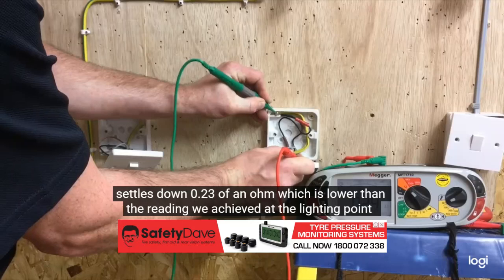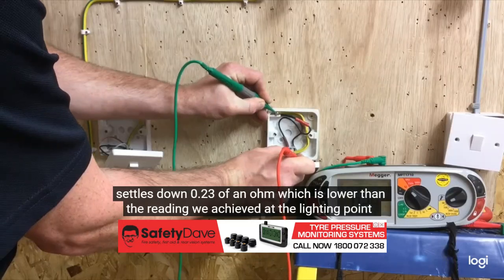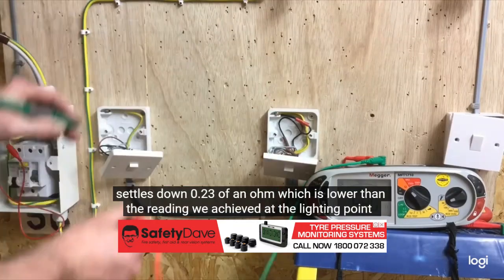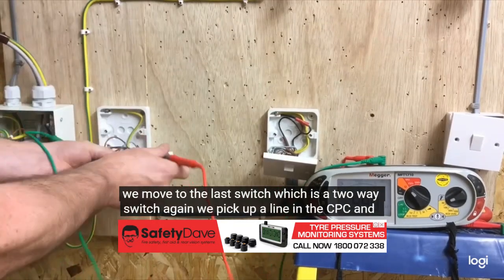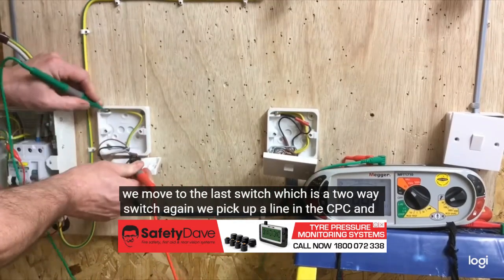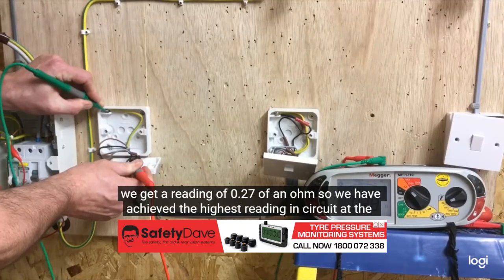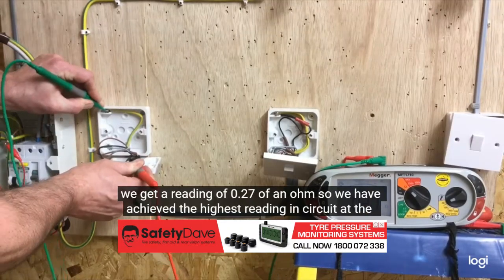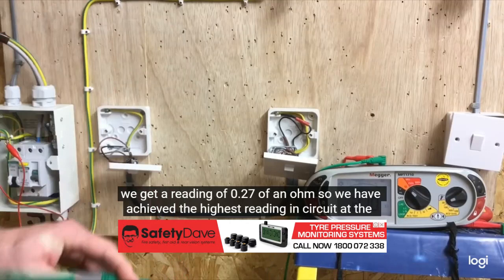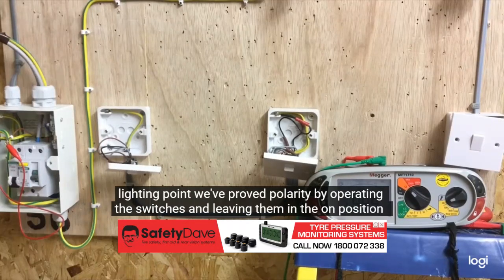We've got a reading of 0.27 of an ohm. So we have achieved the highest reading in circuit at the lighting point. We've proved polarity by operating the switches and leaving them in the on position. We're now ready to move on to our insulation resistance test, which we've got all the covers back on and ensured that all loads are removed. So let's do that next.